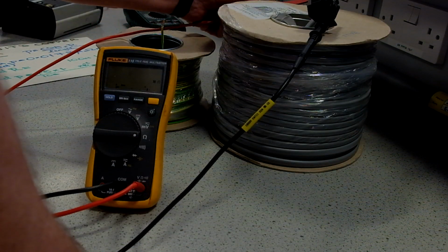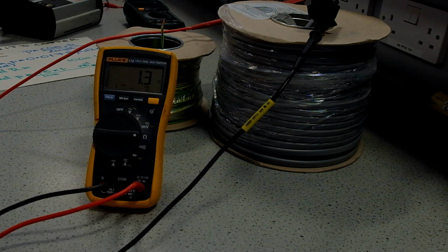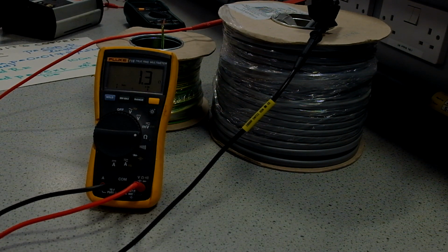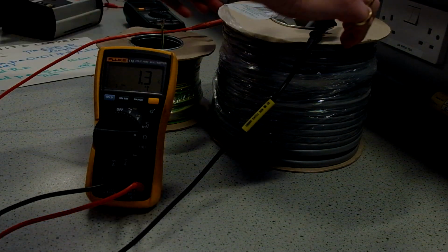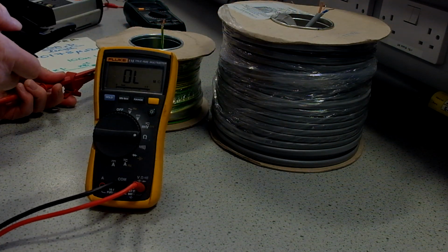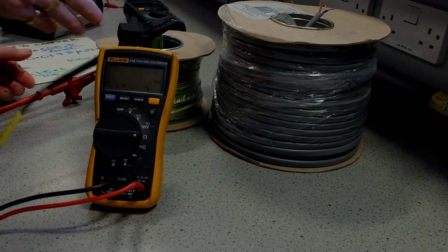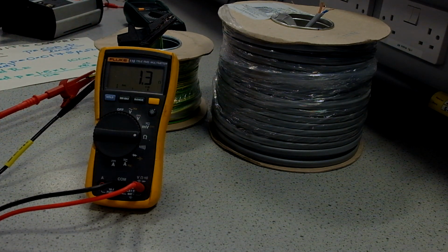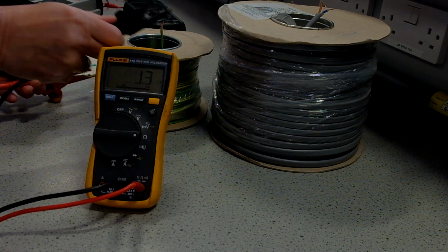We're repeating that, so there we've got 1.3, and if we subtract 0.1 we get 1.2, which matches up with the calibrated meter reading. Let's just double check onto the cable drum. Again, we're repeating experiments. Experiments should be able to be repeated. Again, we're getting 1.2, 1.3. Let's take 1.2 as the reading.